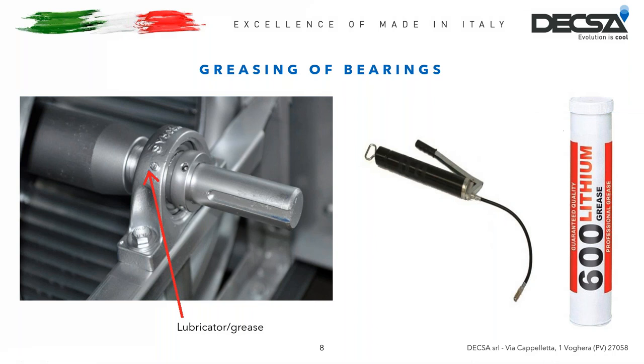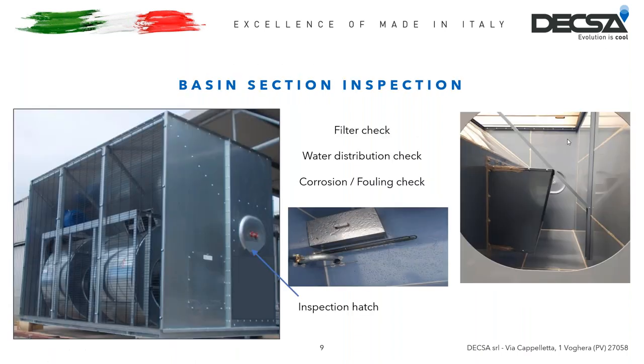Remember: too little grease will cause the bearing to dry out and become damaged. Also, if the grease is too much, it will come out of the bearing seals, collect dirt on the outside, and then introduce it into the bearing — and will damage it too. Now we can proceed to the control of the inside of the water collection basin by removal of the inspection door. After this, it's possible to remove the protection filter of the water outlet connection for cleaning, and also check for signs of scale, corrosion, or rust on the internal panels.